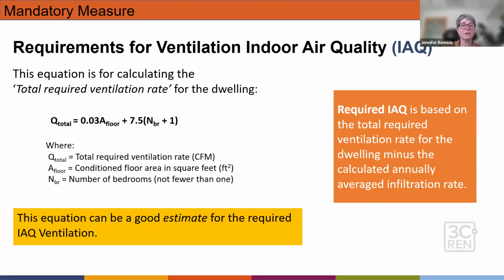So the formula hasn't changed here. I put this in for the architects because you can use it as a good estimate for how much ventilation is needed for an individual dwelling unit or apartment in multifamily. The reason is we're seeing more and more architects planning their ventilation strategies as part of their design, because as space heating moves more towards heat pumps that are not using outside air through the heating and cooling system, you need a separate system that is bringing in the outside air.